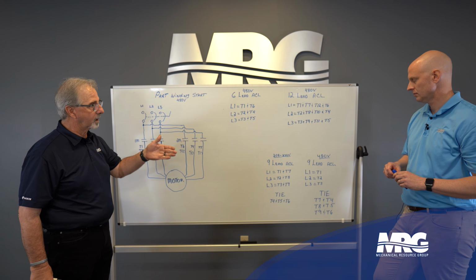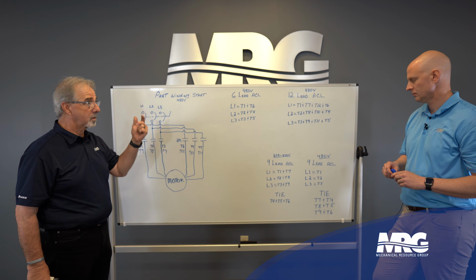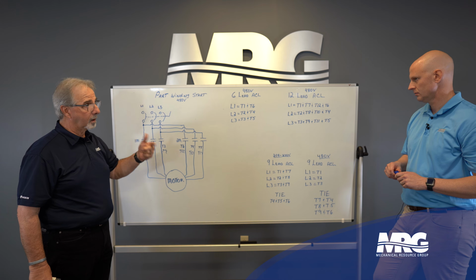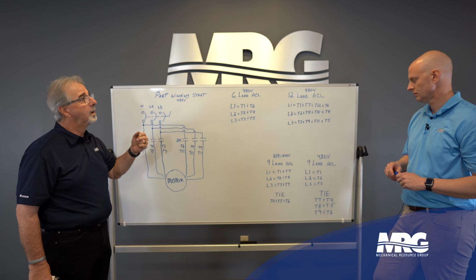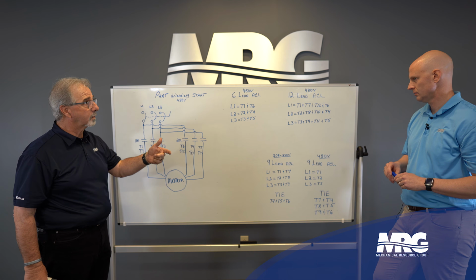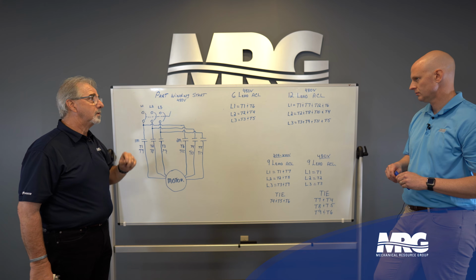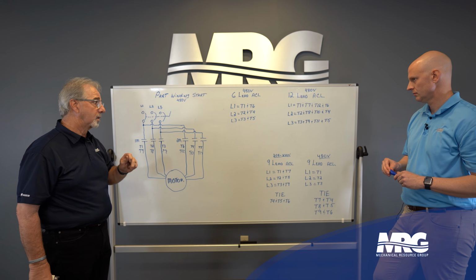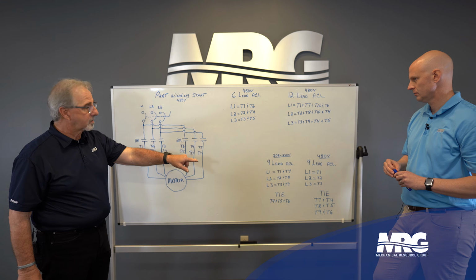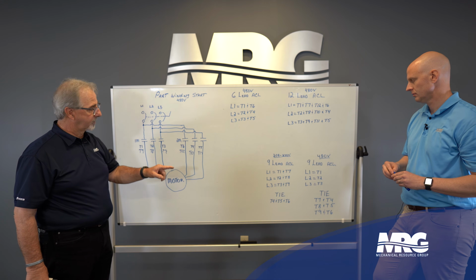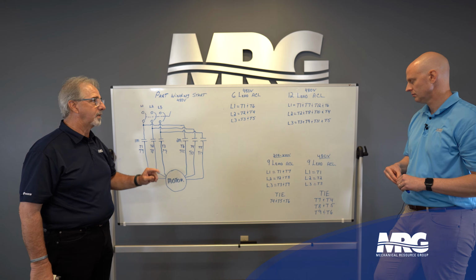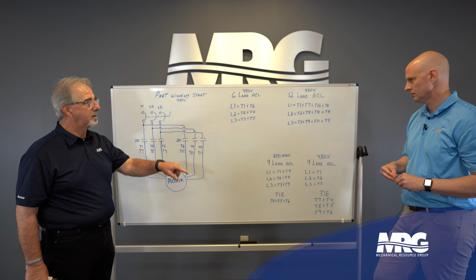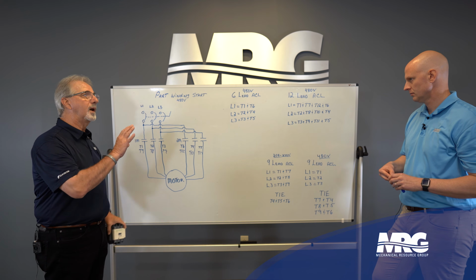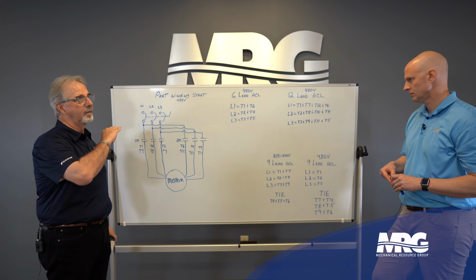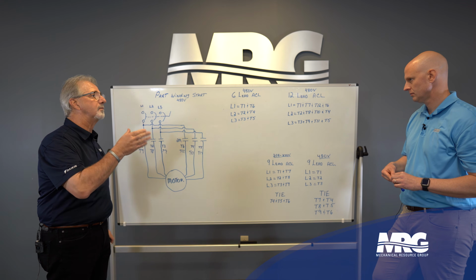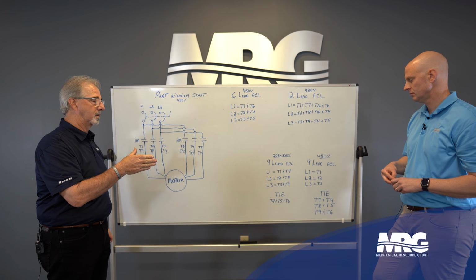If we go to 480 volt, lead L1 is going to be motor lead number 1, L2 is going to be motor lead number 2, L3 is going to be motor lead number 3. But now what we do is we have to make some other connections. Tie 7 and 4 together, cap them off. Tie 8 and 5 together, cap them off. Take T9 and T6 together and cap them off. And what I mean by capping them off is you isolate them and they never see voltage. I don't apply voltage to those leads, okay?